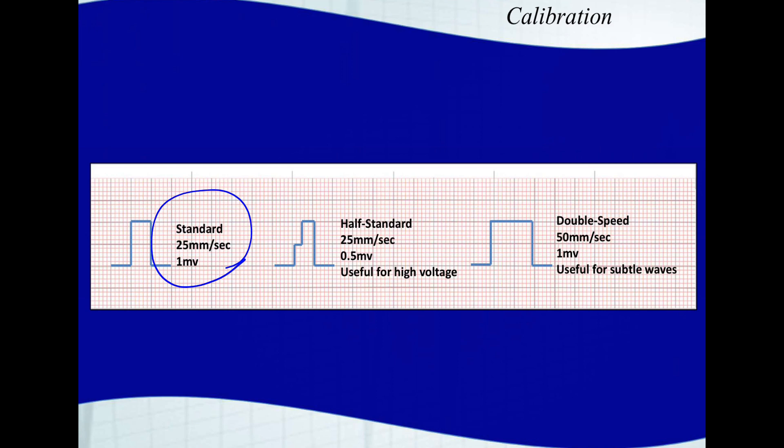If the print speed is faster, it'll create a wider calibration. A common European print speed is 50 millimeters per second, so you get this double width calibration mark. Sometimes you have a half standard calibration mark, which is often used if a patient has some sort of cardiomegaly or hypertrophy. It shows up as very large complexes, which may make it difficult to interpret, so you can calibrate the EKG to half standard.